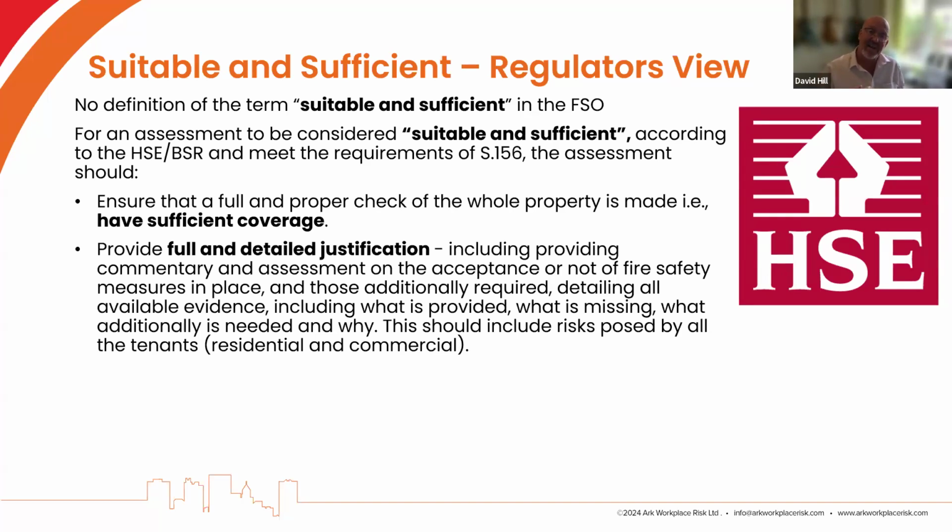And we've got to provide an assessment on the acceptance or not of the fire safety measures that are actually in place, as well as determining exactly what additional elements are required based upon the assessment. And all of that has got to include the evidence that you are basing it upon, what is provided, what's missing, what additionally is going to be required and why. And also, where are those risks placed? Where are they posed from? Is it in a residential area? Is it a commercial area? Is it in the common area? We need to understand, in order for that risk assessment to be suitable and sufficient under the new elements here, what and where the risks are coming from.